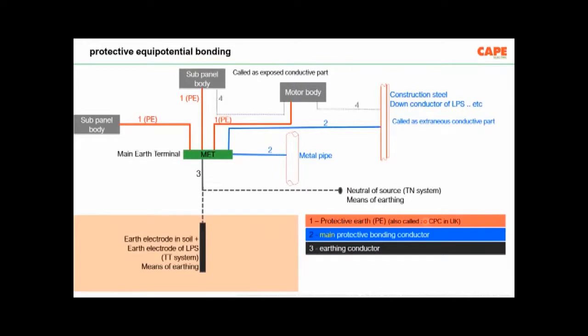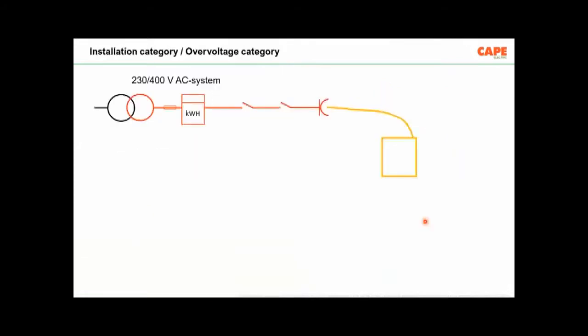Every building, the first part, if you wanted to protect any electronics, you must have the protective equipotential bonding. Of course, it is implemented mainly for shock, protecting people from shock hazard, but it has got a role in protecting electronics as well, because now the concept of functional earthing comes into the picture, and you have to integrate protective earthing and functional earthing in a building. So if you don't have a protective earthing system in your building, of course, you forget about EMI, EMC. You cannot even have basic safety. Your building will catch fire. If you have so many earth pits all around, your building will catch fire during a fault.